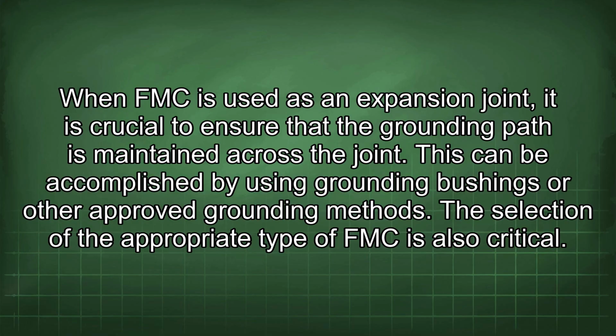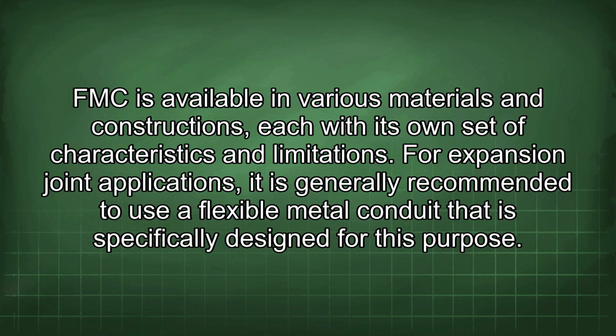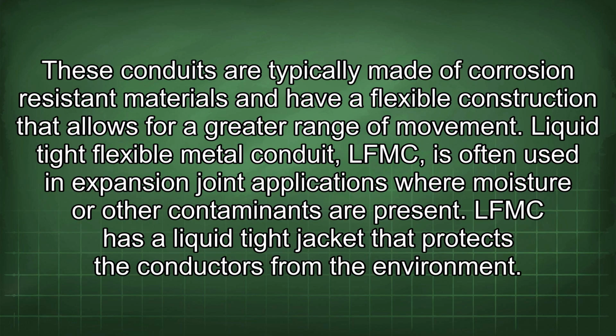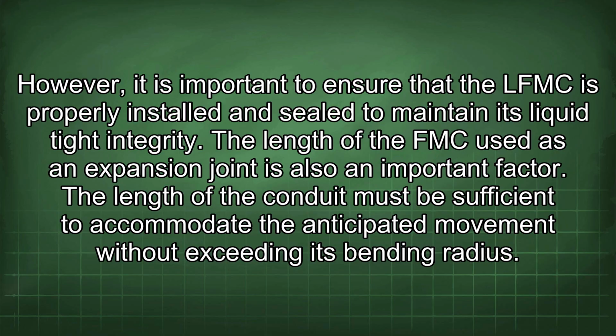The selection of the appropriate type of FMC is also critical. FMC is available in various materials and constructions, each with its own set of characteristics and limitations. For expansion joint applications, it is generally recommended to use a flexible metal conduit that is specifically designed for this purpose. These conduits are typically made of corrosion-resistant materials and have a flexible construction that allows for a greater range of movement. Liquid-tight flexible metal conduit (LFMC) is often used in expansion joint applications where moisture or other contaminants are present. LFMC has a liquid-tight jacket that protects the conductors from the environment. However, it is important to ensure that the LFMC is properly installed and sealed to maintain its liquid-tight integrity.